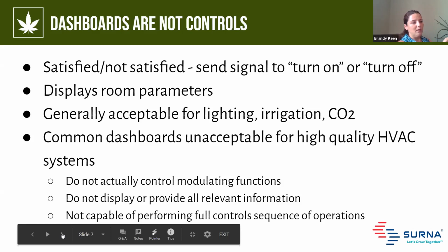By that I mean, if we're measuring the leaving air temperature, we need to modulate this valve in 10% increments until we're satisfied. Those sorts of things aren't generally provided by most front-end controls companies.